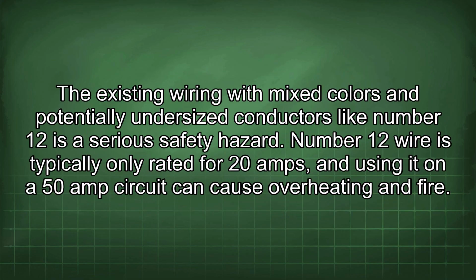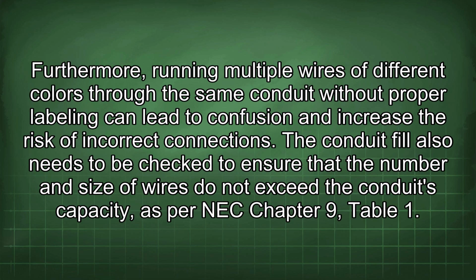The existing wiring with mixed colors and potentially undersized conductors like number 12 is a serious safety hazard. Number 12 wire is typically only rated for 20 amps, and using it on a 50 amp circuit can cause overheating and fire. Furthermore, running multiple wires of different colors through the same conduit without proper labeling can lead to confusion and increase the risk of incorrect connections.